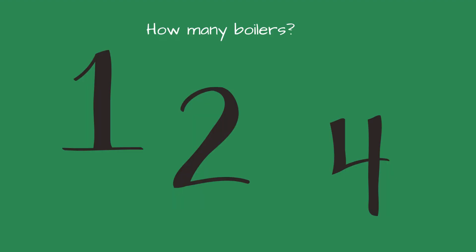How many boilers? Once you have calculated the heating load for the building, you have to decide how many boilers you will use. While one boiler is less expensive, I would be hesitant to do that because if something breaks down, the customer will call you without heat. The minimum I would use is 2, and I prefer using 4. Four boilers will give greater backup capacity, better seasonal efficiency, and a higher turndown ratio.